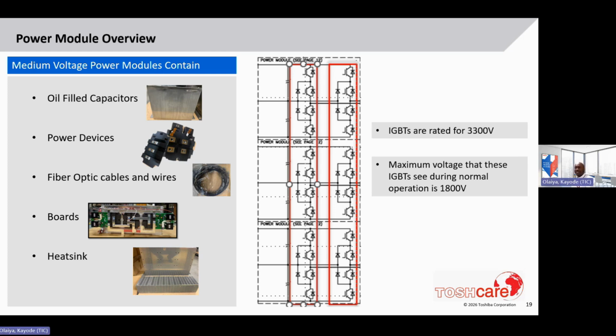We have the power devices shown there. These are the clamping diodes and the IGBTs. The clamping diodes are to make sure that the power modules all reference the same neutral. And the IGBTs, of course, are what switch to generate that AC voltage from the rectified DC. We also have fiber optic cables and wires connected to the different devices, the boards, the IGBTs, and all of these are for carrying signals to ultimately the drive control board, which is where they will all end up.